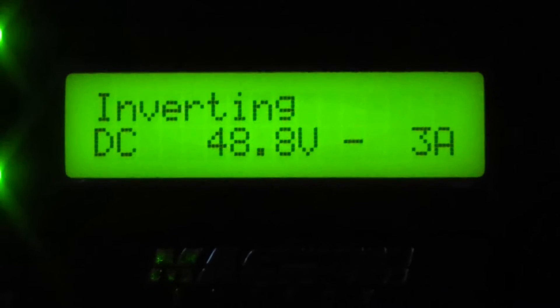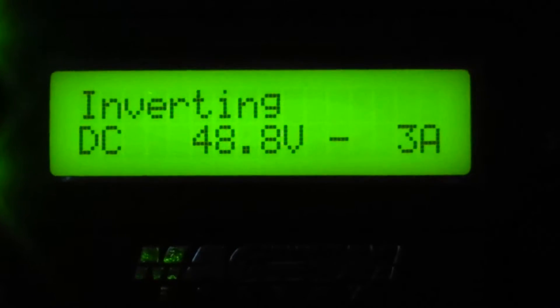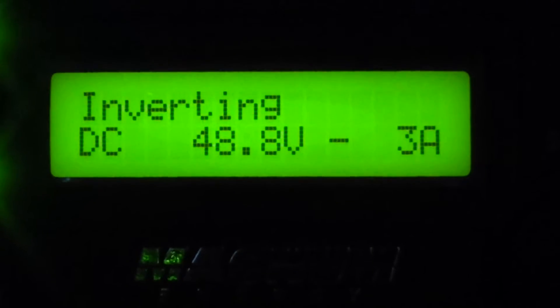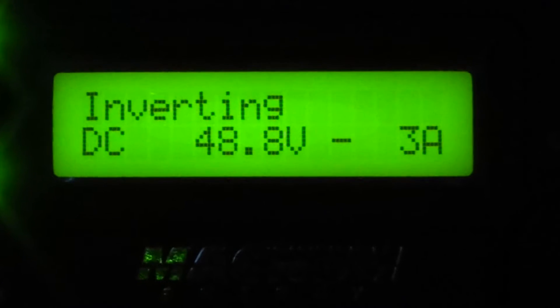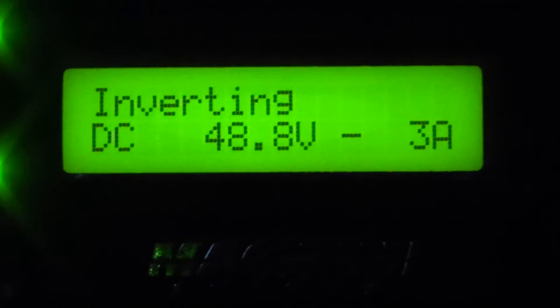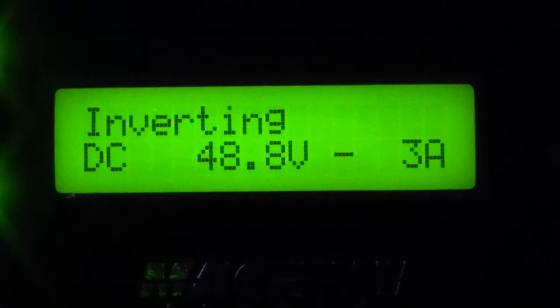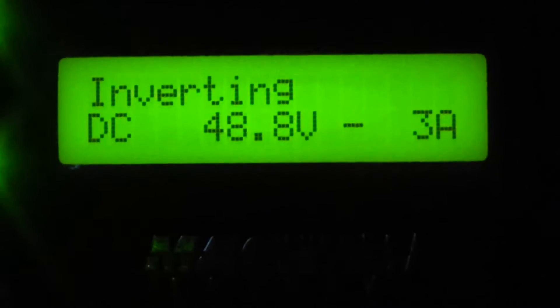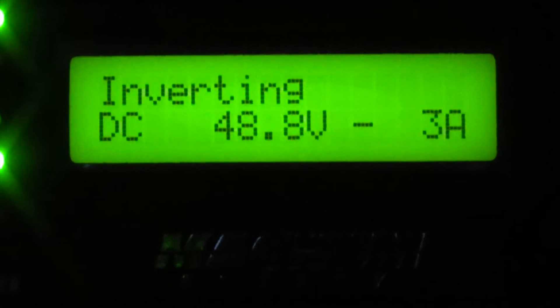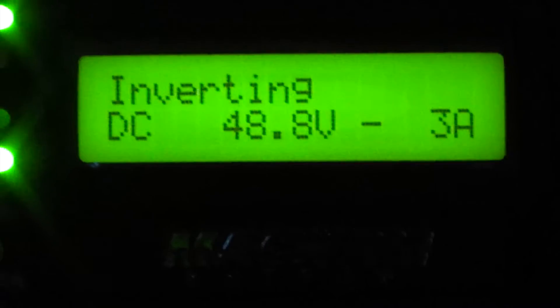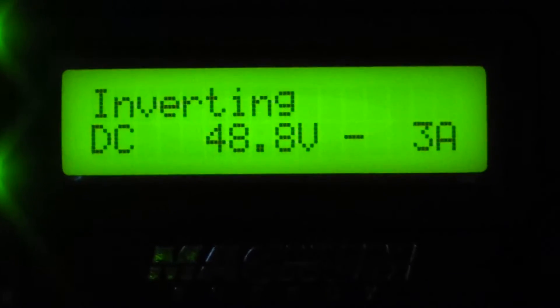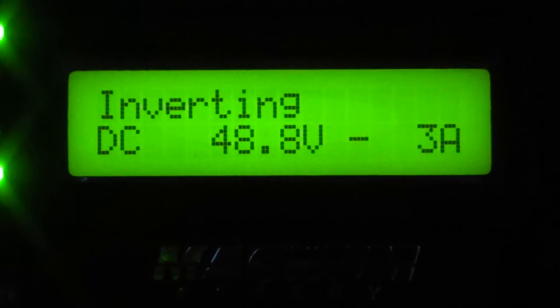And here on the volts, the DC 48.8 volt, I have a problem here with it dropping fairly quick for my load overnight. That's due to temperature. It was about 20 degrees outside, and voltage will drop in that cold temperature. Your amps, not so much. So in a cold environment, keep a close eye on your voltage, not so much the state of charge. And I know in the manual it says the state of charge is the most accurate for charging.